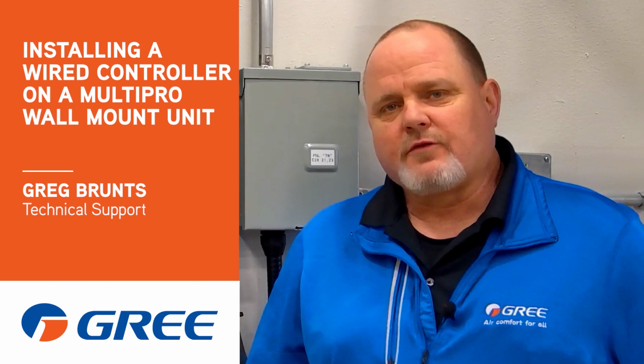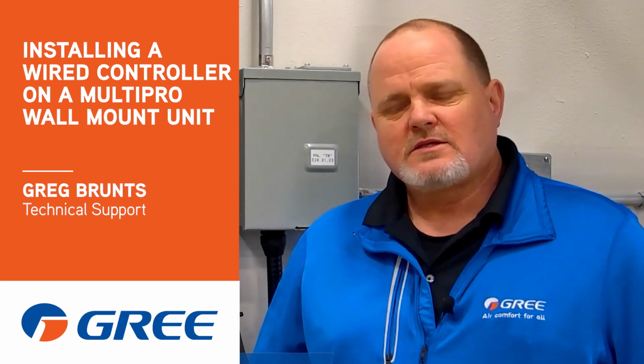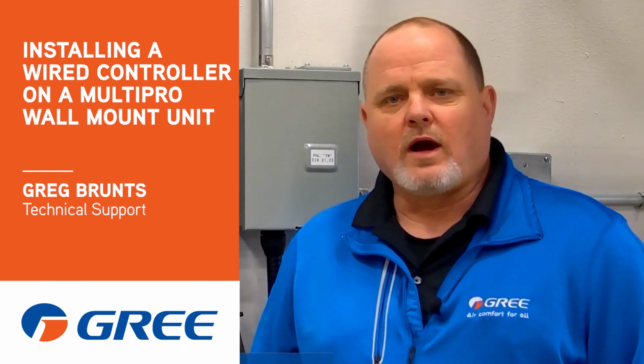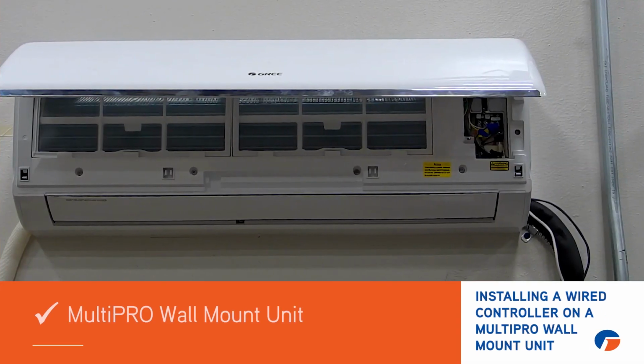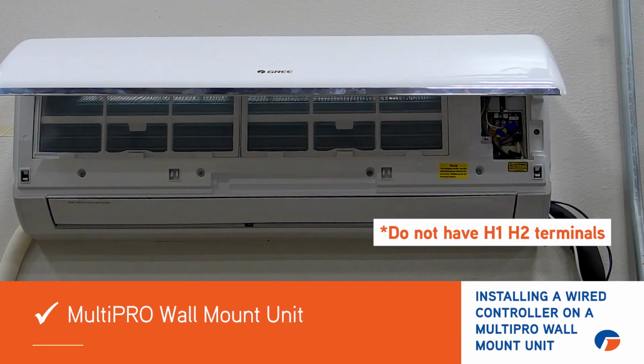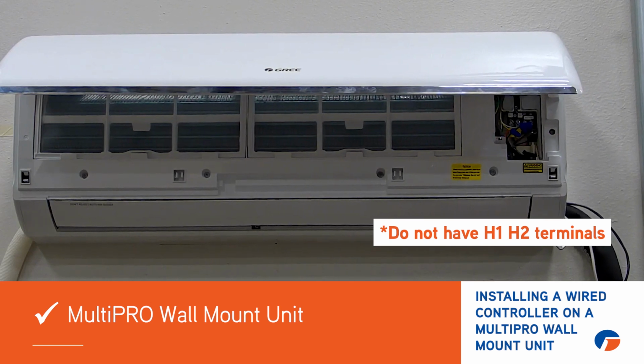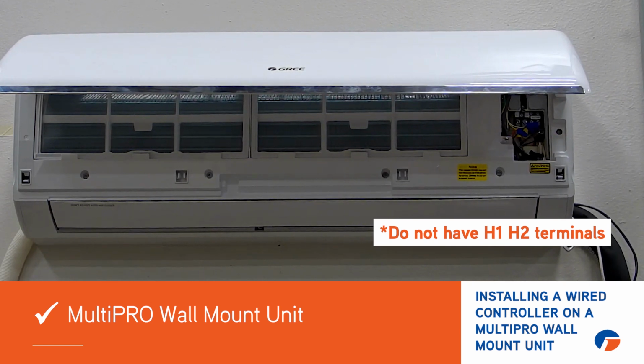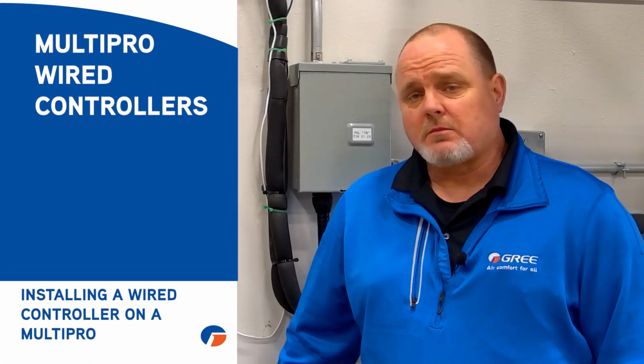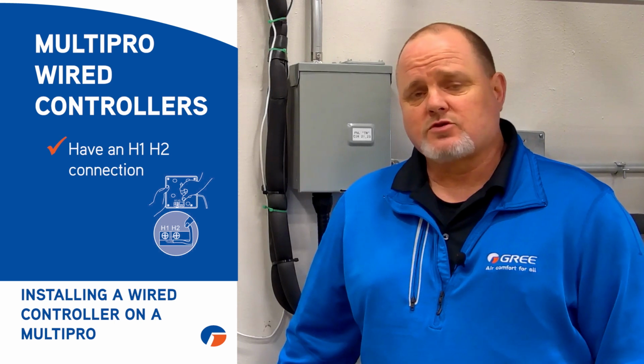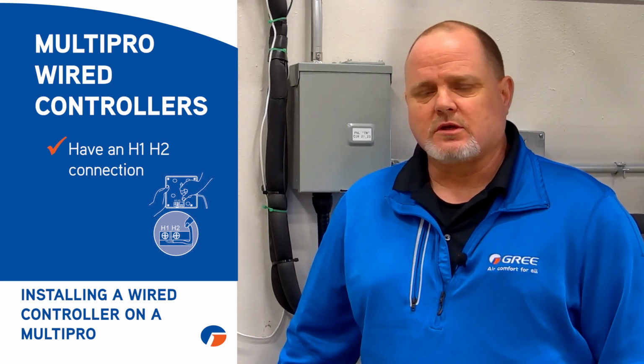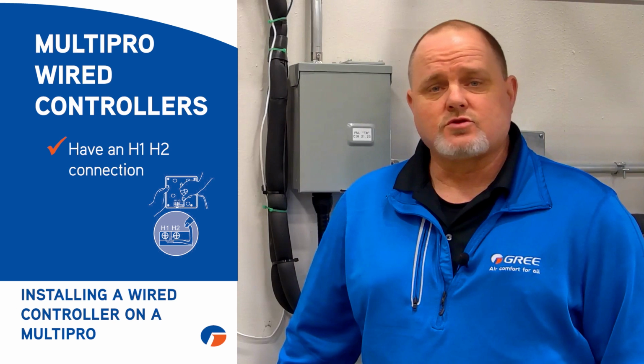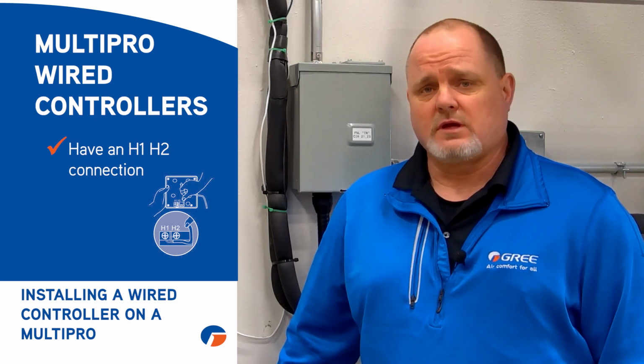Hi, Greg with GREE here from our labs down here in Atlanta. I want to share with you today that if you need to install a wired controller on a MultiPRO wall mount unit, they don't have the H1 and H2 terminals like you would see in a lot of the other MultiPRO equipment. But you can install a wired controller. Remember, on the wired controllers on MultiPRO systems, on the back of the wired controller it has an H1 and H2 connection, and you just use an 18-2 stranded wire going from there to the indoor unit. So if you need to hook up a wired controller, this is how you're going to do it. Let's jump right into it.